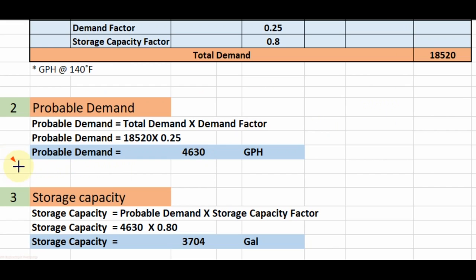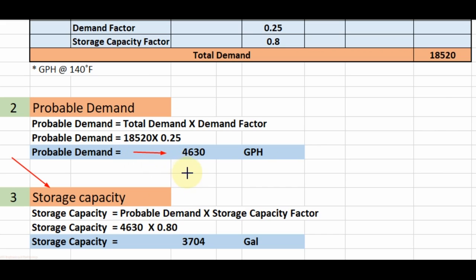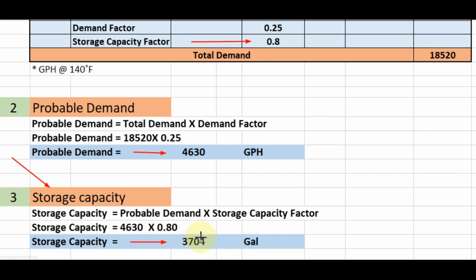Now we will calculate the storage capacity, or the size of the water heater for our building. The formula is: storage capacity equals probable demand multiplied by storage capacity factor. The probable demand is 4,630 GPH and the storage capacity factor is 0.80. When we multiply 4,630 by 0.80 we get 3,704 Gal. This is the storage capacity or the size of water heater required for our building.